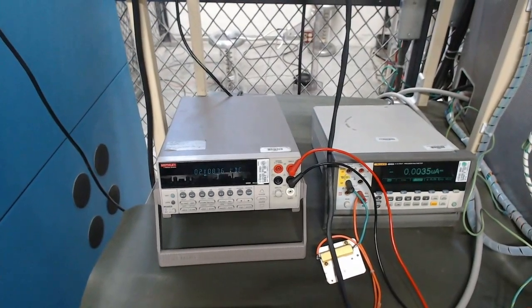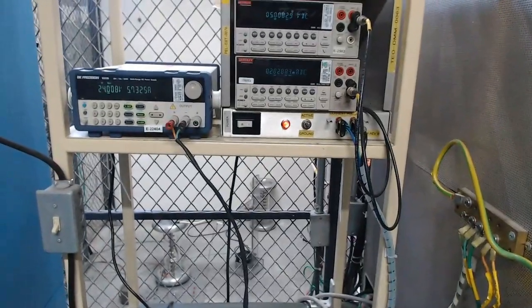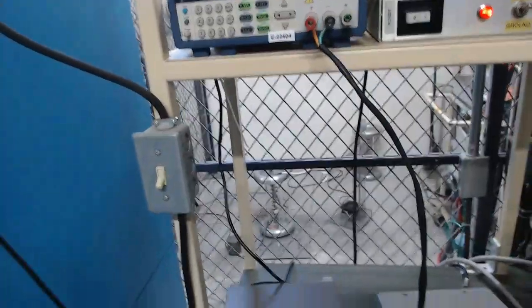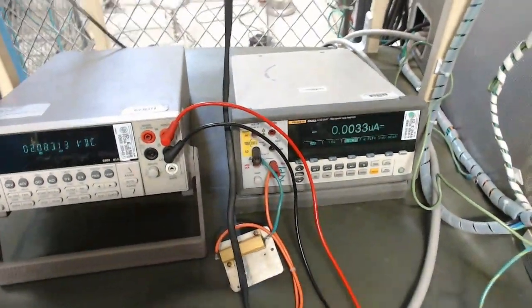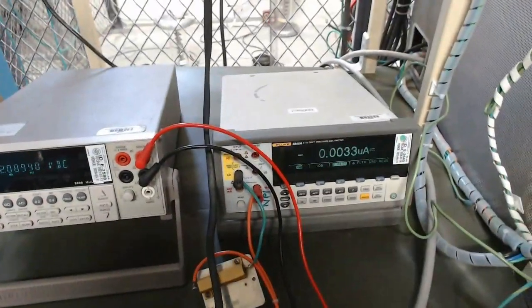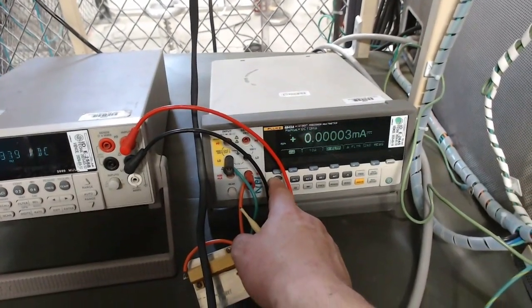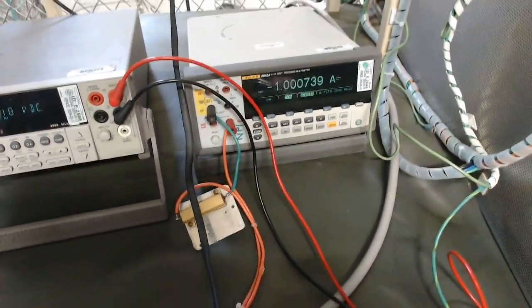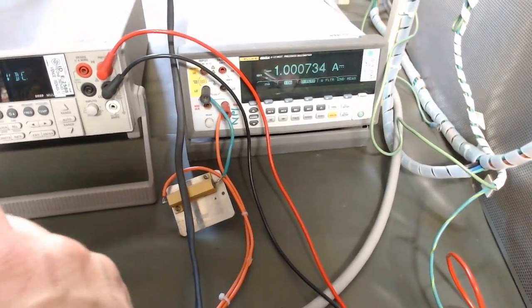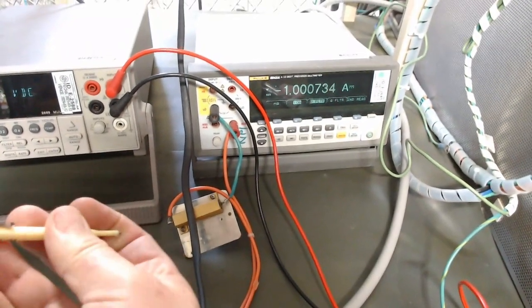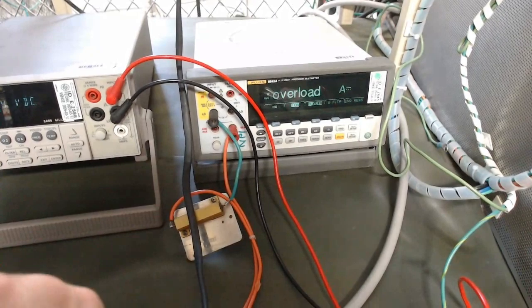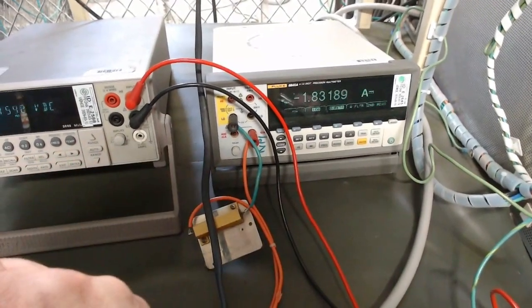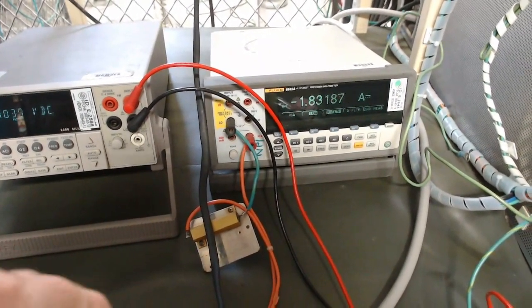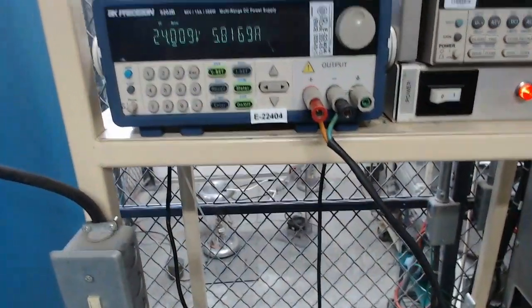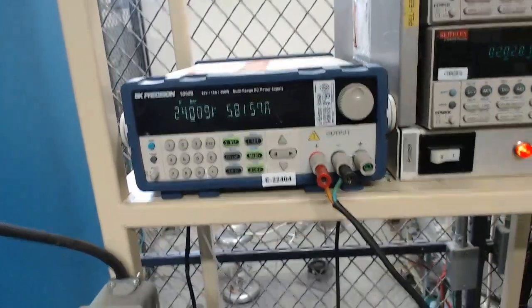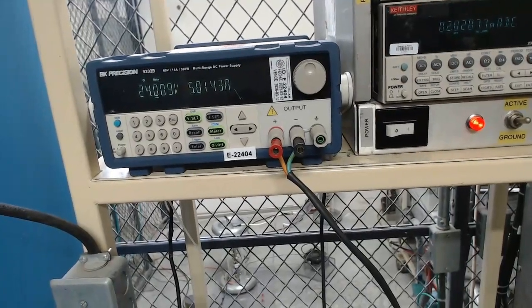Unit is set to maximum rated voltage again, including maximum filament, and input current is recorded, ensuring input current remains less than 7.75 A. In this case, input current is 5.81 amps, which is within specification. Value is recorded into the datasheet before proceeding with the next tests.